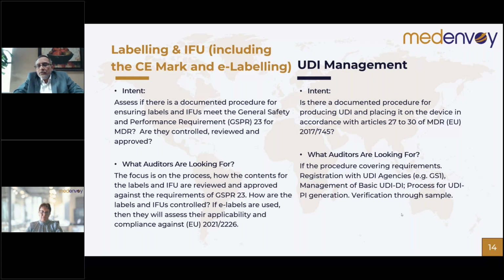UDI is another area of interest. So how do you manage UDI, your unique device identification? So do you have a procedure? Do you have identified which agency you will be using for UDI management? And the procedure should identify the management of UDI-DI and UDI-PI and all those elements.